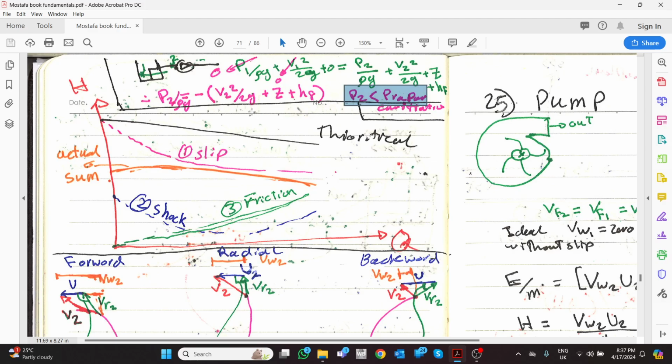That is, inside the pump itself, a cavitation can occur, which means if your pressure here is above the vapor pressure, it's okay, safe for the pipe, but when the water runs here, cavitation will occur because of the moving itself, because you're increasing the velocity before increasing the pressure, so a cavitation can happen on the blade.